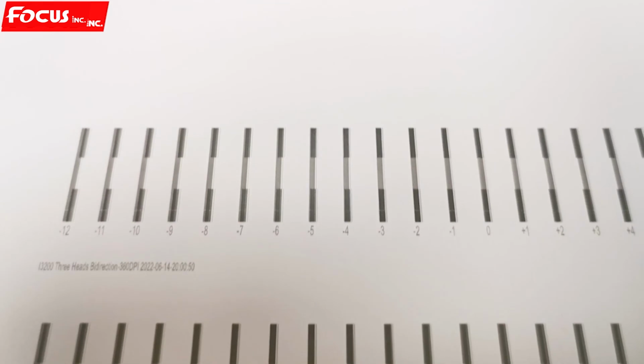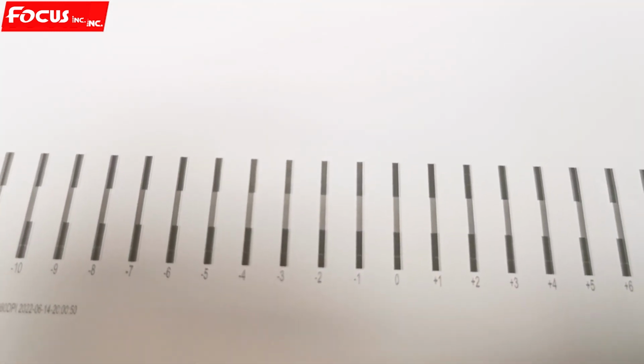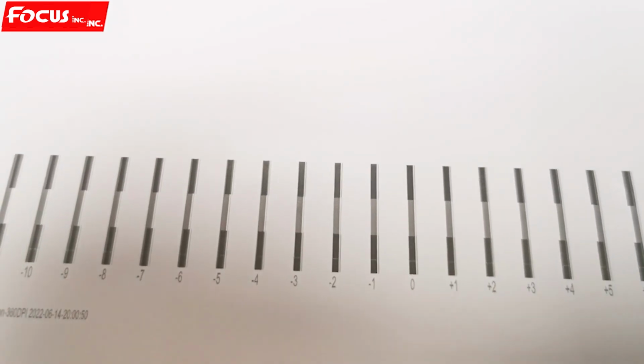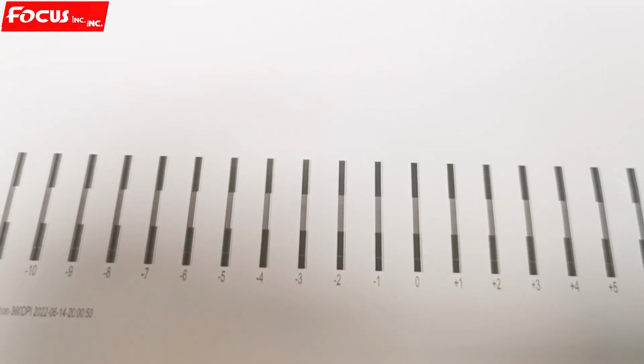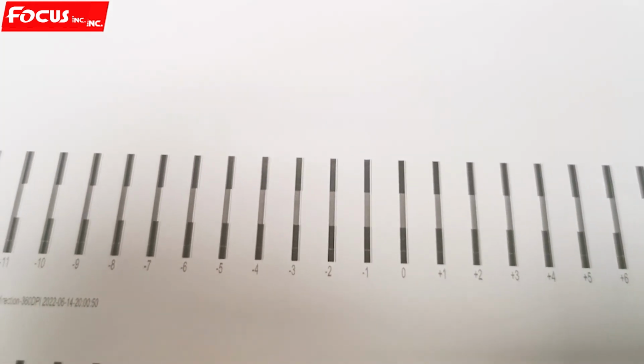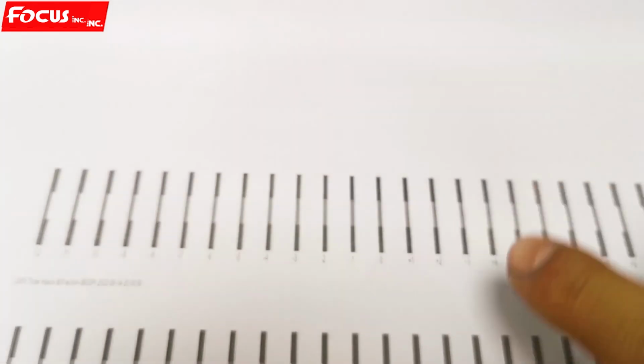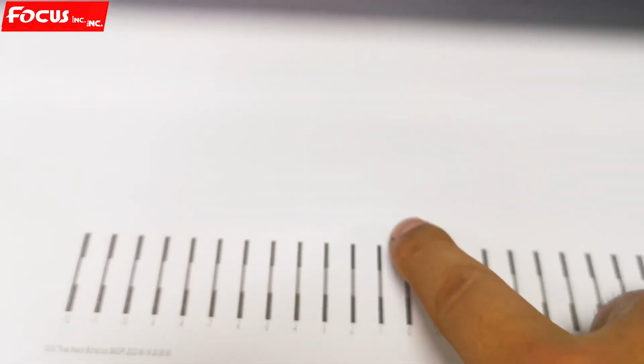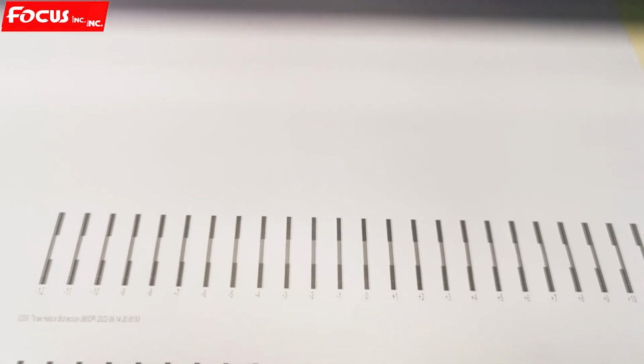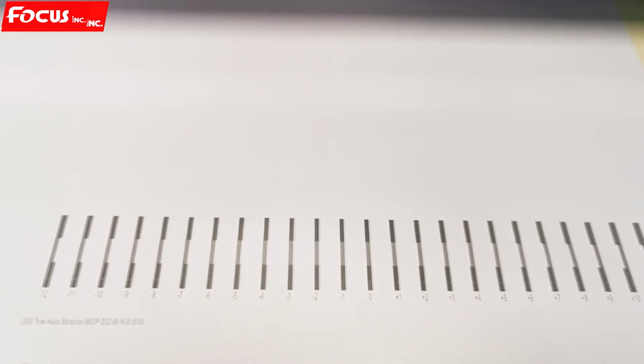So here it's back. Now 0 is the best. Top, bottom, middle. Anyway, we just make sure that at the 0 position the top and bottom do not overlap to the left or to the right, and form a straight line. That will be a good calibration for the bidirection. So this is the procedure to do the bidirection color offset, the bidirection calibration.